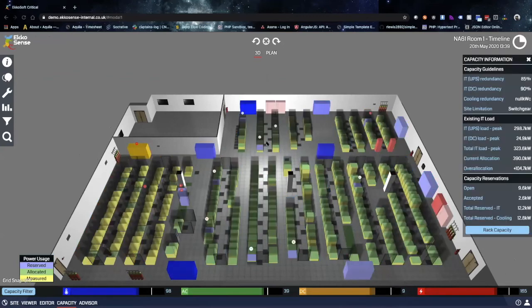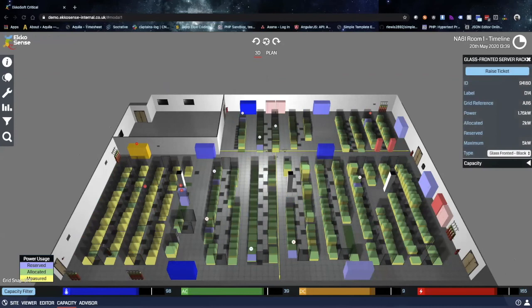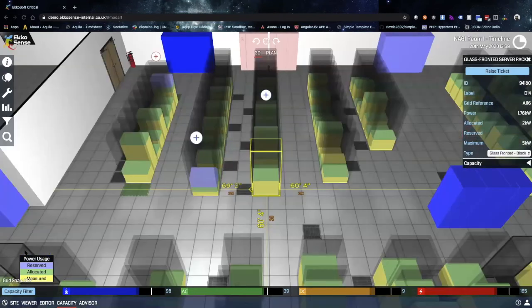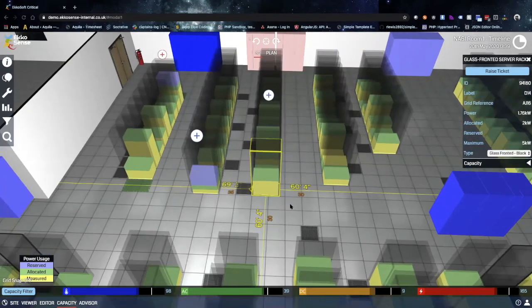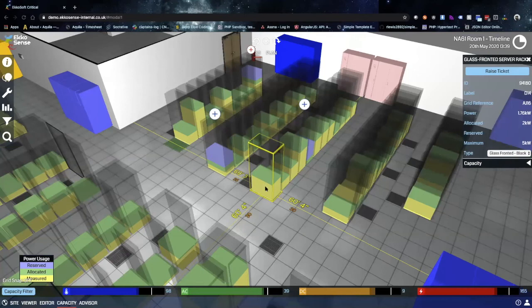So let's go ahead and look at a rack real quick. We can see the legend on the left has also changed. Now we're looking at the yellow color, which is actual measured power from the PDU units in this rack. Then the green color is allocated power. That's something that the end user sets themselves, allocating a certain level of power to this rack. And then we can see the purple in this rack is reserved power.